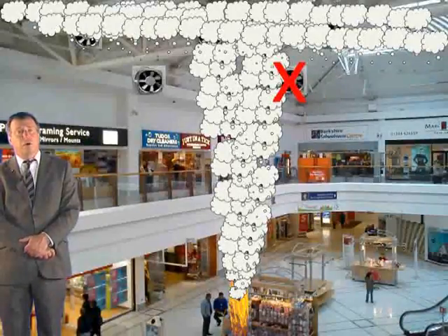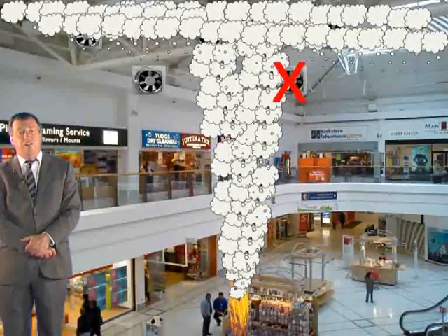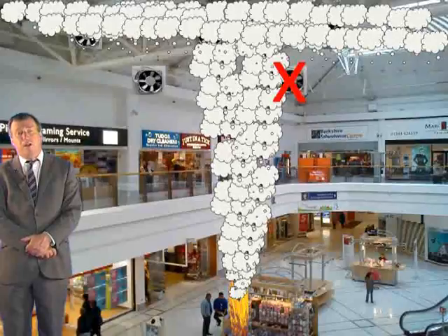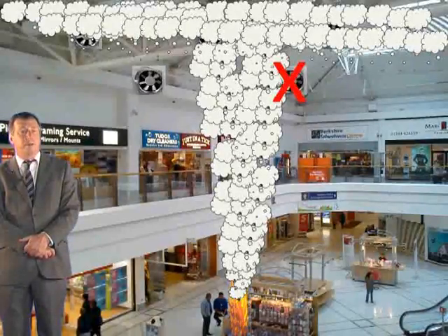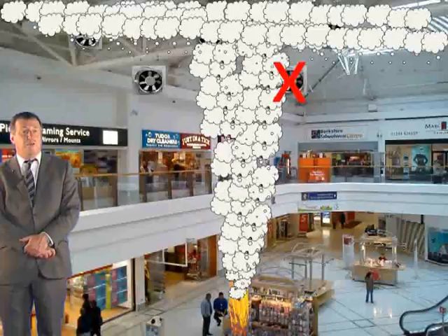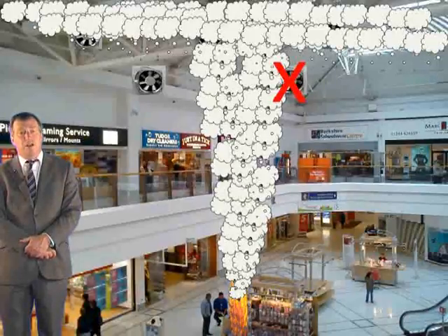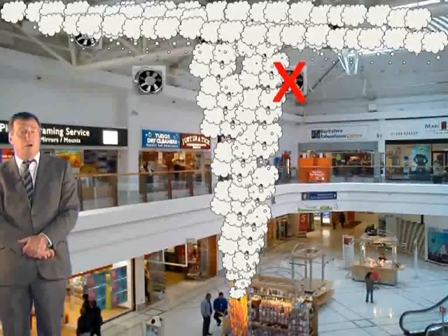This discounting of one of the fans is not required where there is no possibility of losing a fan to the fire. This would be the case in a divided building, perhaps where there is no fire load directly underneath the fans or the intakes. It is not assumed that any fan will be lost for any other reasons, such as simple mechanical failure. The fans must have duplicate power supplies and should be subject to regular servicing, so they should be reliable. Standards are laid down in BS EN 12101 Part 3, 2002.